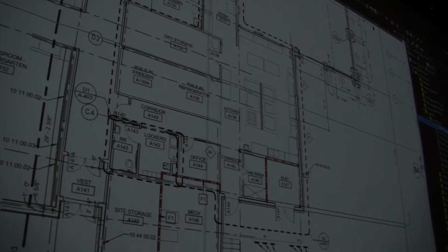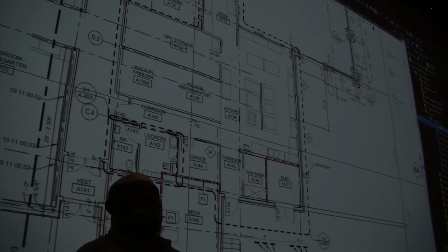Yeah, if you can consider, for instance, on this project, you had the kitchen, mechanical room, main electrical room, all in one corner, and everything branches out from there. For instance, APS has a spec requirement: all those VAVs have to be out in the corridor. Because, okay, fine, during passing period, you got a guy on a ladder right outside the classroom door, but he's not in the classroom interrupting the students, and the students and teacher don't have to move to another classroom because there's a maintenance issue with the air conditioning system for that classroom.